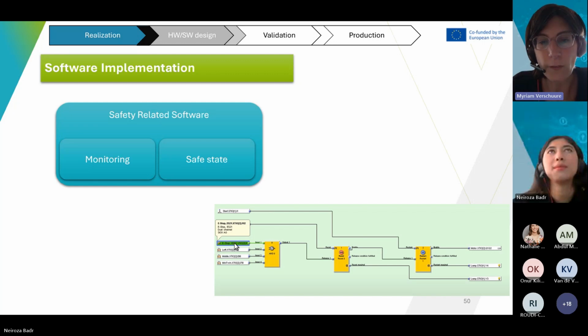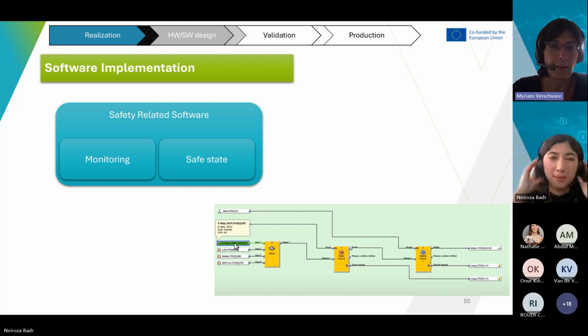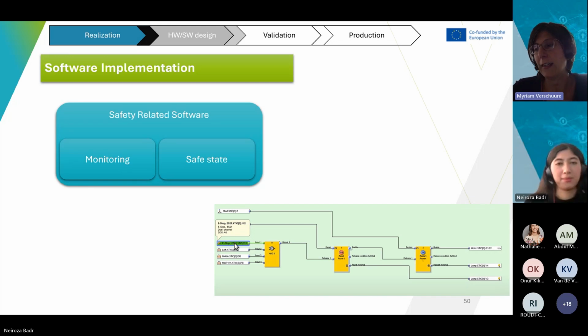If you are lucky, you may have at your disposition from your manufacturer, for instance for PLCs, a simplified code generation like the example shown below, where you can use certain predefined functions and blocks that you assemble together. That makes your life easier, but it doesn't mean that by assembling blocks prepared by others it's all safe on its own. You still need proper implementation and proper testing of your software, and no spaghetti code. In safety, it's very important to have a proper structure, and the simpler your code is, the less prone to errors it is.